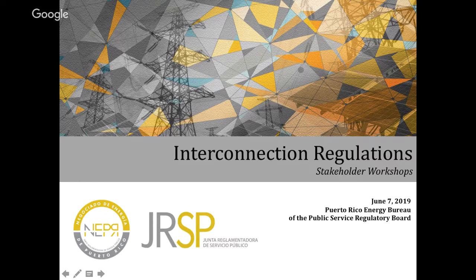Yes, of course. As you mentioned, this provides GD interconnection requisites up to 20 megawatts. As you know, the Puerto Rico electric grid isn't necessarily the same as what we see in US interconnected systems. Our system is unique. Our voltage levels are lower than what we may see in other jurisdictions, and specifically in distribution, our voltages are also lower. Our voltage goes up to 13,200 volts.